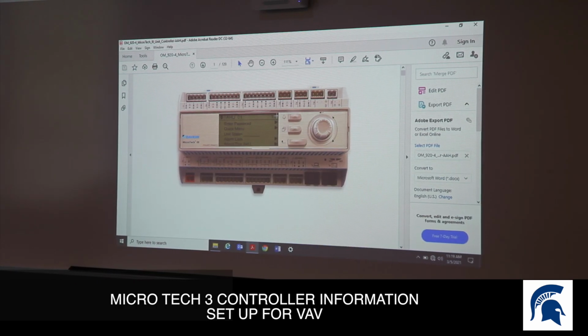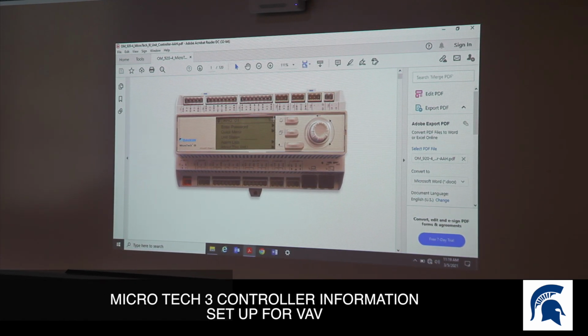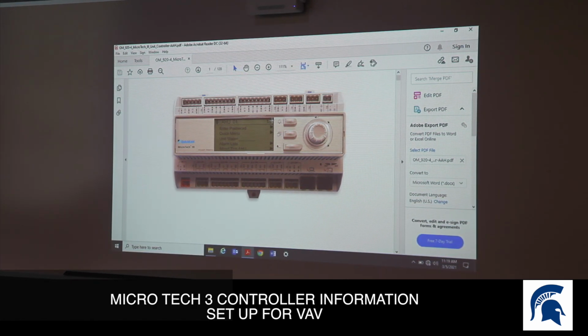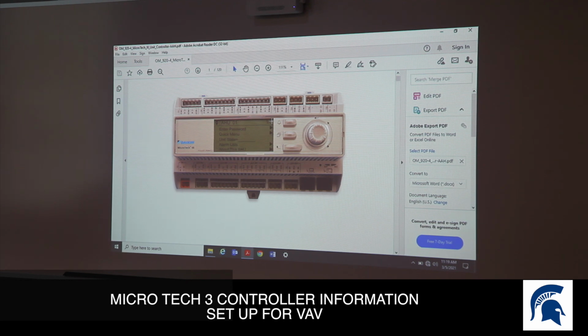Sure. One of the things that Daikin does, as opposed to some other manufacturers, is it stages things up sequentially and slowly, okay? So you hit that switch, it's not gonna bam right on. The first delay you're gonna see is probably a 60-second delay for the power relay that monitors your three-phase to come back, okay? After that, things happen kind of quick, but I'll show you, because there's LED indicators on all of these machines. See these things?